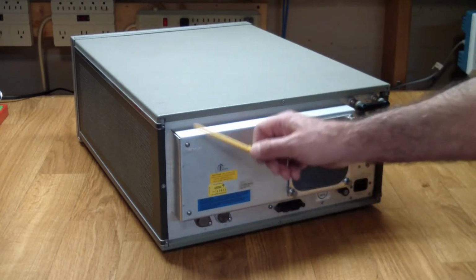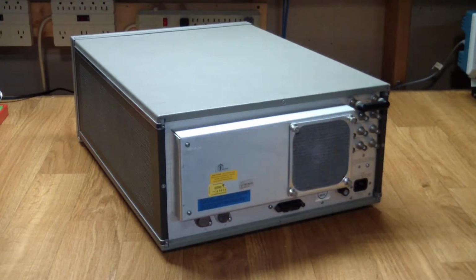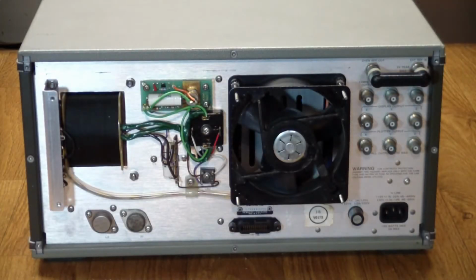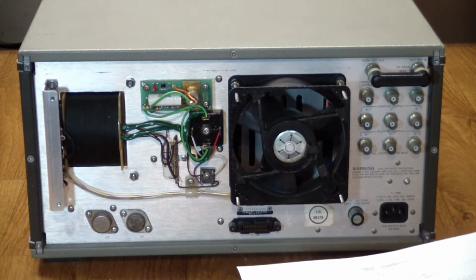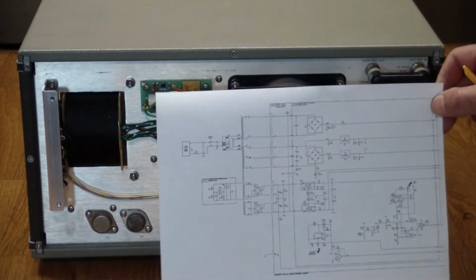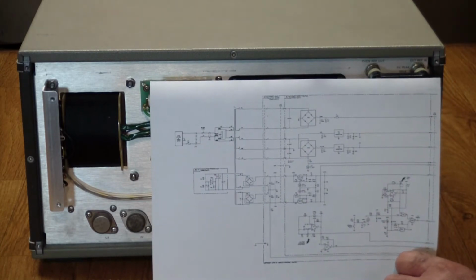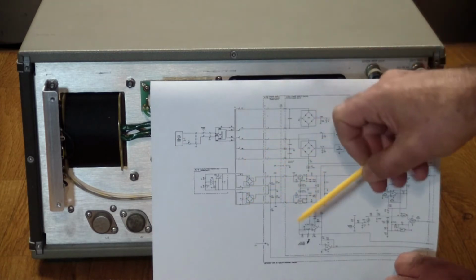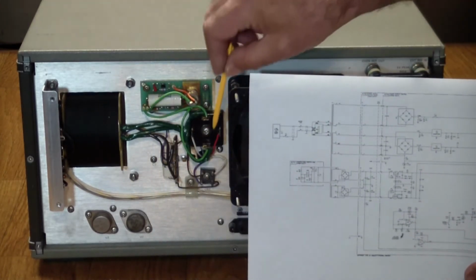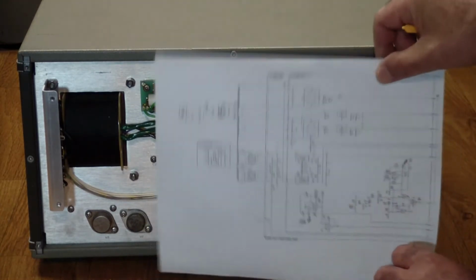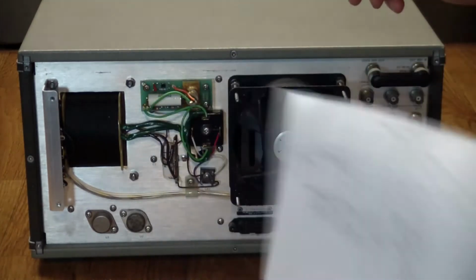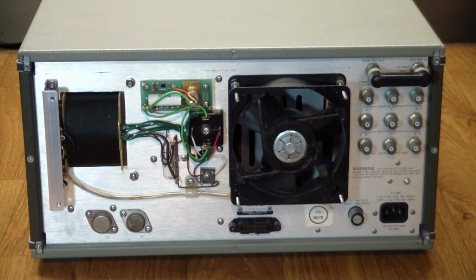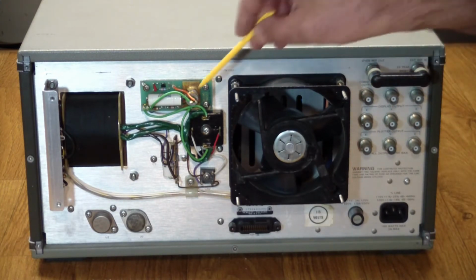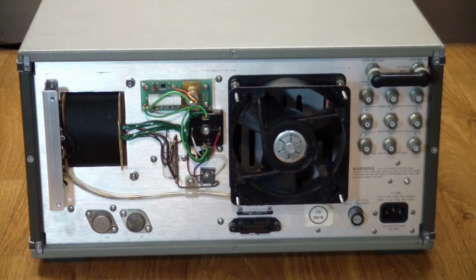Now to get off the back, I have a few screws to remove, and let's see what's underneath there. Here it is with the back removed, and what we can see here is the initial stages of what's happening with the transformer. Here are all of our secondary tabs. There are two bridges, here and here, generating 50 volts DC, and some protection circuitry over here, which is also located here. I did turn on power and check the bridge outputs, and there is plus minus 50 volts there, so our problems are a little bit deeper.